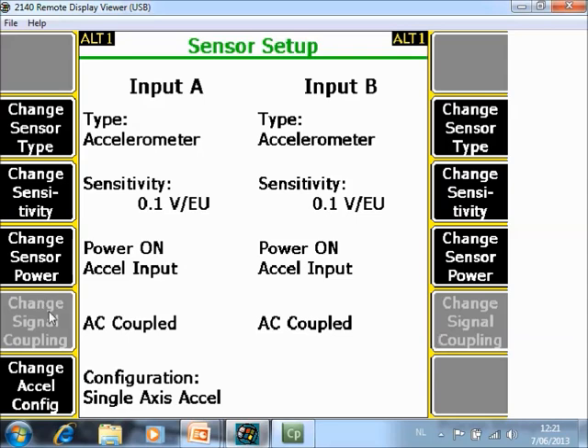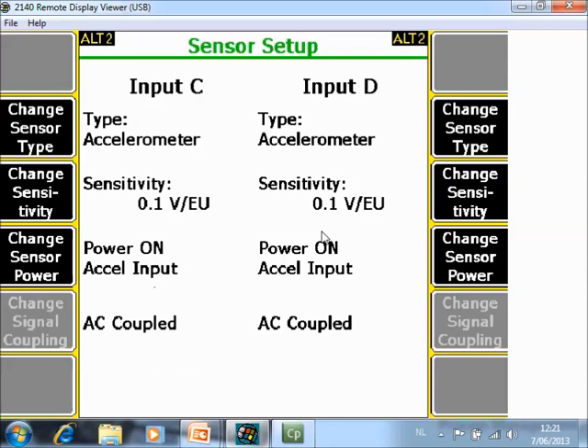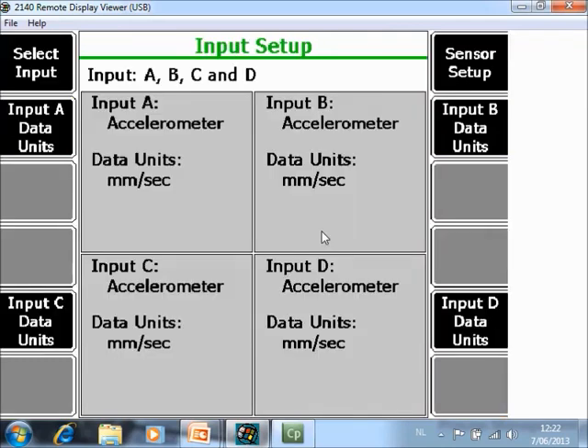In this example we are working with an accelerometer 100 millivolt per engineering units power on. That is a typical configuration for a normal accelerometer. Channel B is identical, Channel C and D also, so the four sensors are correctly configured.